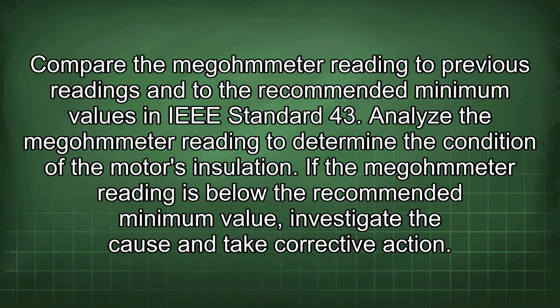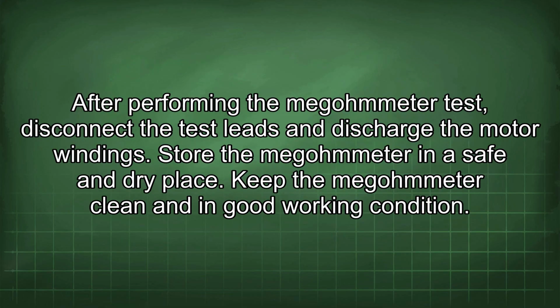Compare the megohmmeter reading to previous readings and to the recommended minimum values in IEEE Standard 43. Analyze the megohmmeter reading to determine the condition of the motor's insulation. If the megohmmeter reading is below the recommended minimum value, investigate the cause and take corrective action. After performing the megohmmeter test, disconnect the test leads and discharge the motor windings.